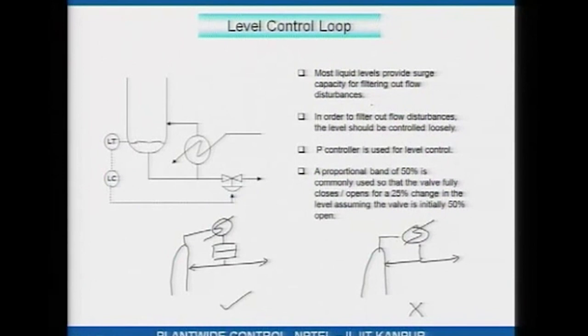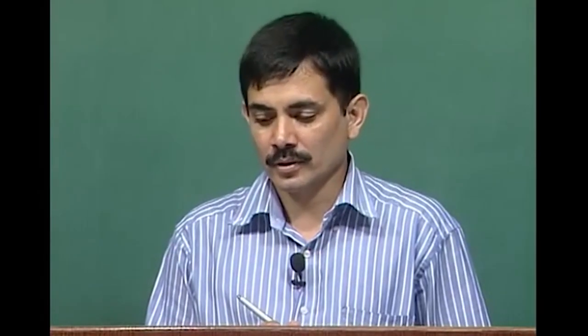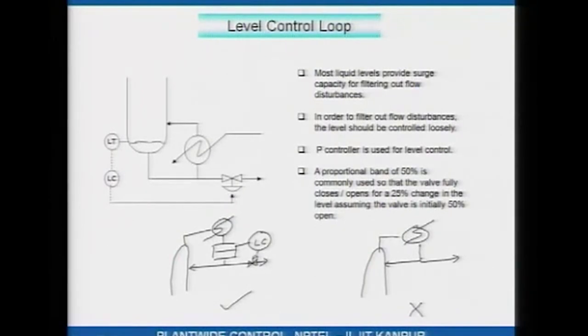Since the purpose of surge capacity is to filter out flow disturbances, the level should be controlled loosely. If the level controller is tuned to be extremely tight, the level will not fluctuate at all, defeating the very purpose of putting in that reflux drum. The drum was installed so that flow disturbances can be averaged out by allowing changes in level. Tight level control defeats the purpose of that surge capacity. Levels should be loosely controlled — they are like shock absorbers in a car, provided to dampen disturbances for smooth plant operation.